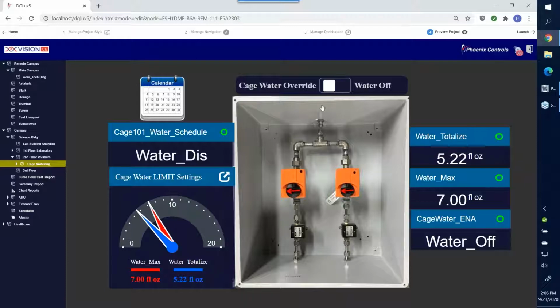So here's an actual cutaway of the panel, and the way the sequence works is pretty easy. They would put in a totalized value. In this case, we have it set for 7 fluid ounces, and anytime there was water usage, it could be water, juice, it really didn't matter, if it was above 7, then they wanted to disable and not allow the watering to take place. But then they also said they wanted it scheduled.